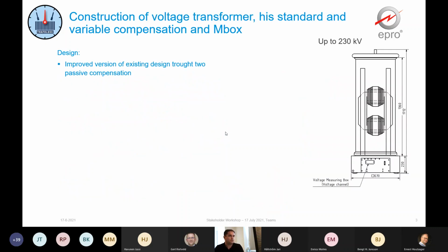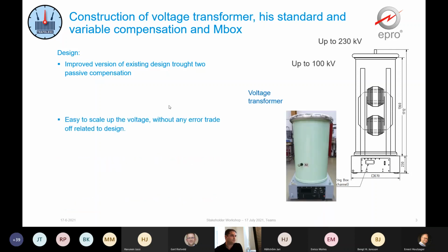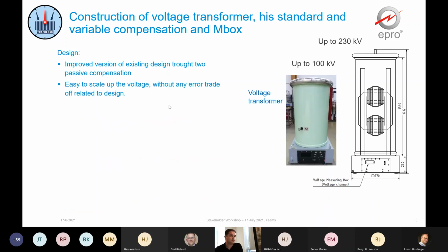The first thing we had to do was to design and build a voltage transformer up to 100 kV. The reason why we go up to 100 kV instead of initially 230 kV is because we think the system can be easily scaled up without any error trade-off. In fact, using higher voltage designs, we can handle the error even much better. So there was one good reason to go further with 100 kV.